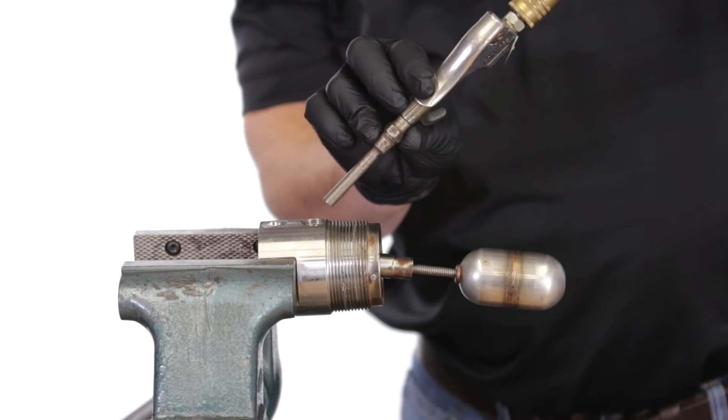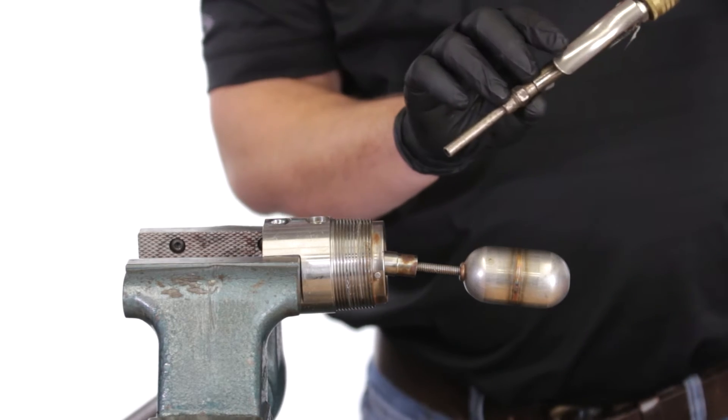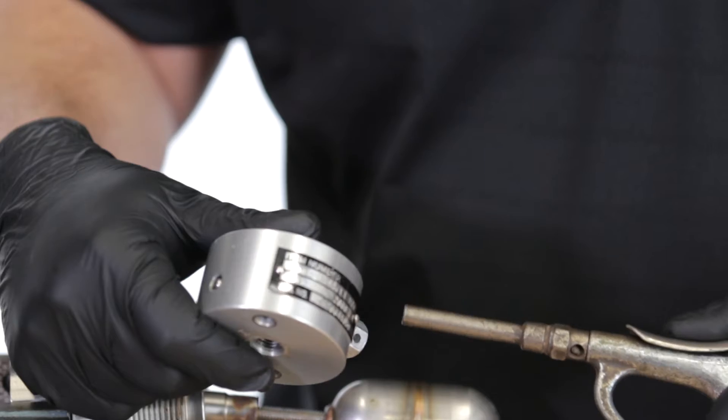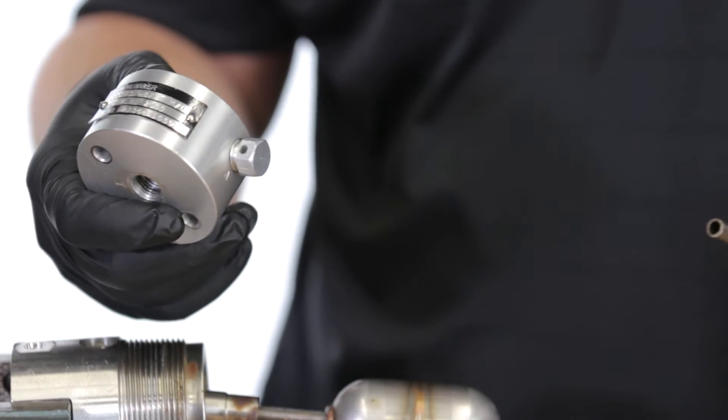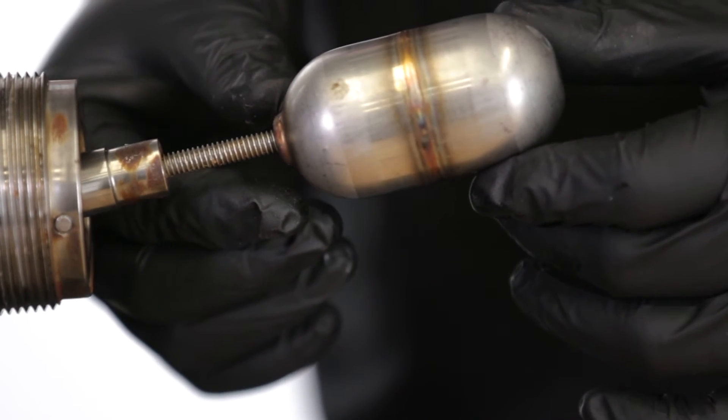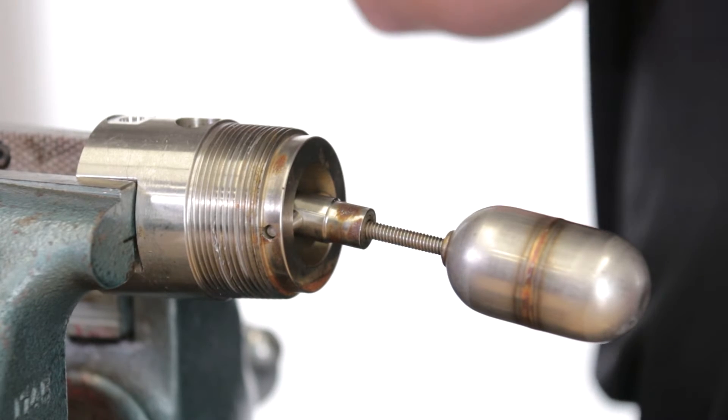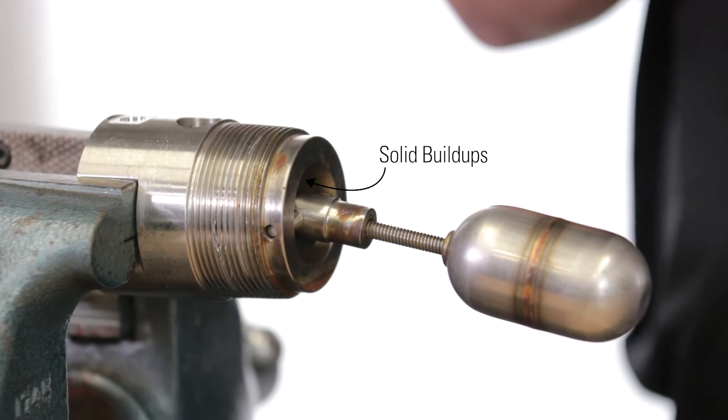With the level switch disassembled, next inspect and clean each component with compressed air to make sure the body is free from contaminants. If you use brake cleaner, wipe it clean before assembly. Clear the vent plugs of any debris. Inspect the float for any punctures or damage. You may need to inspect the float lever more closely or clean any solid buildup inside the level switch.